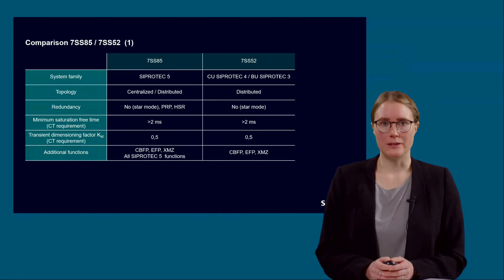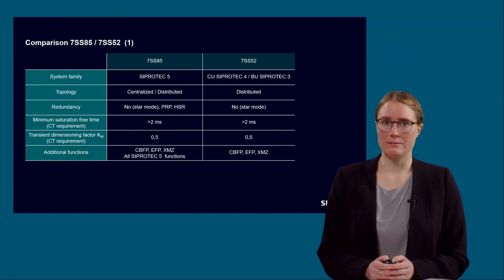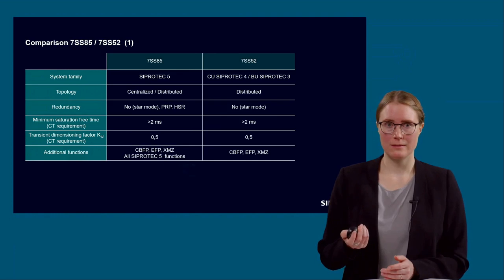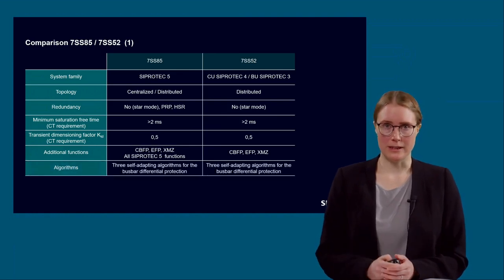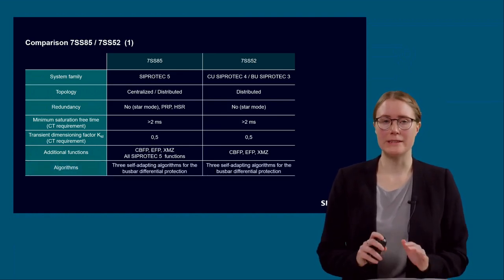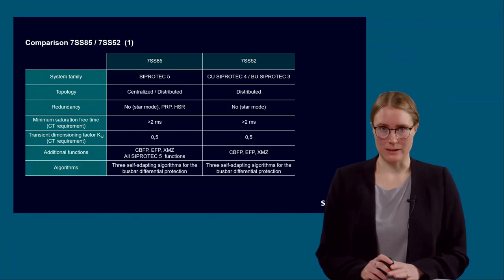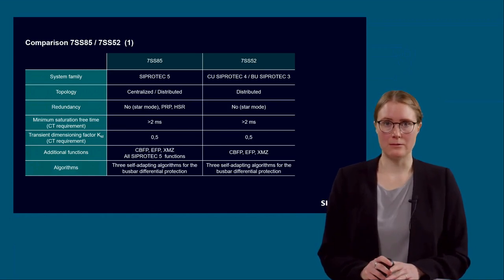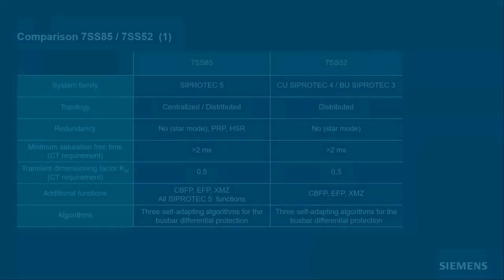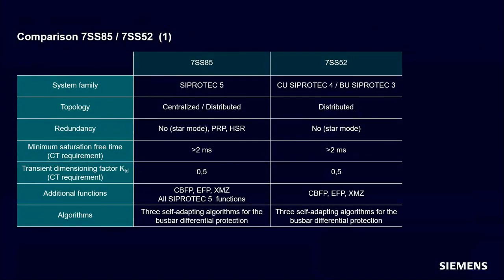The typical functions for busbar protection, like circuit breaker failure protection and end-fault protection, are of course available in SIPROTEC 4 and SIPROTEC 5. The protection algorithms are completely the same in both devices. We have the 3 self-adapting algorithms for the differential protection: the 1 out of 1, the 2 out of 2 algorithm, and the algorithm with the filtered measured values.